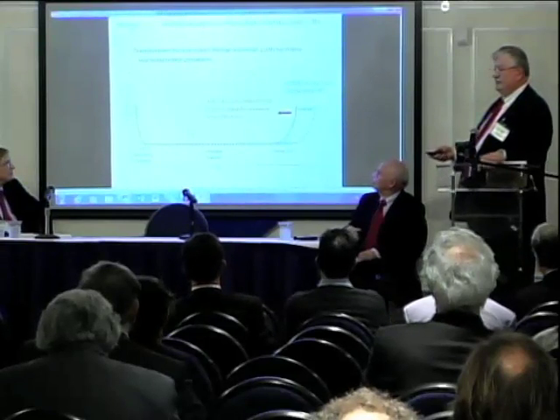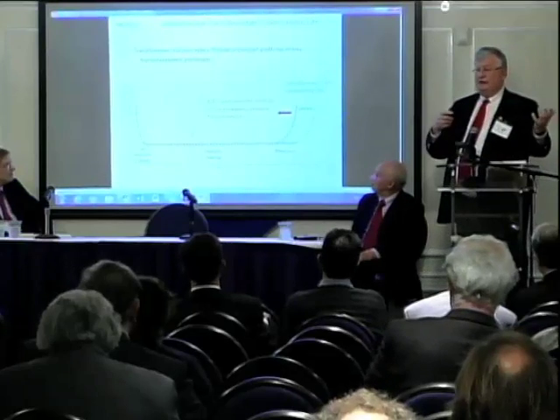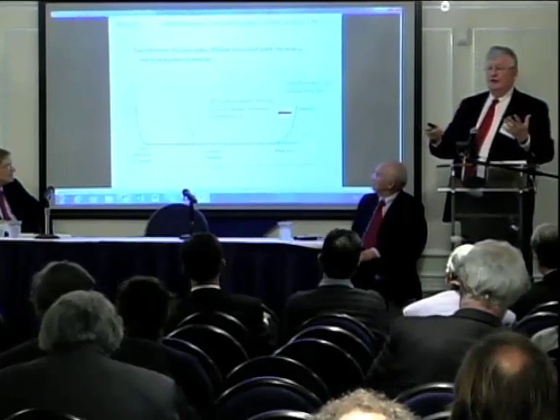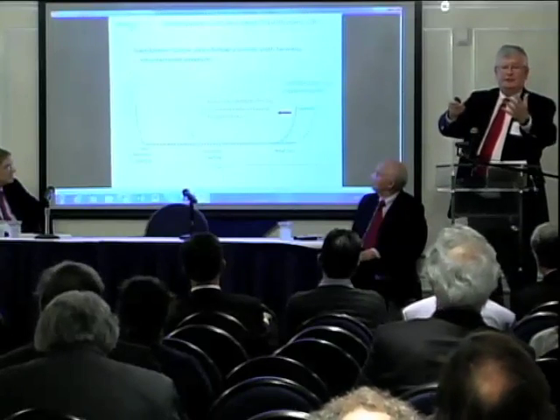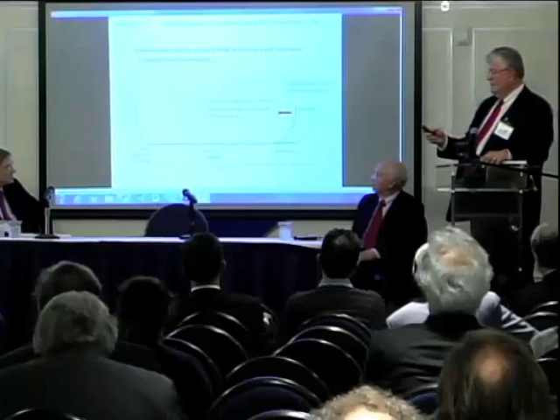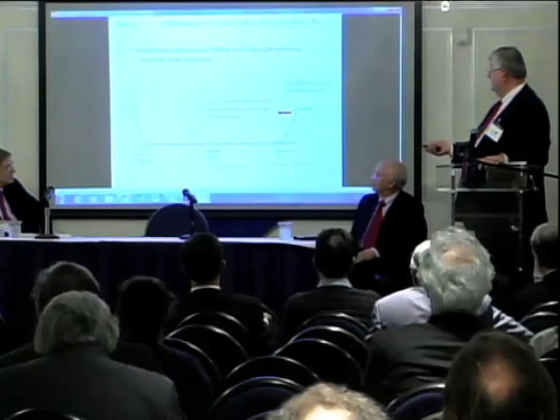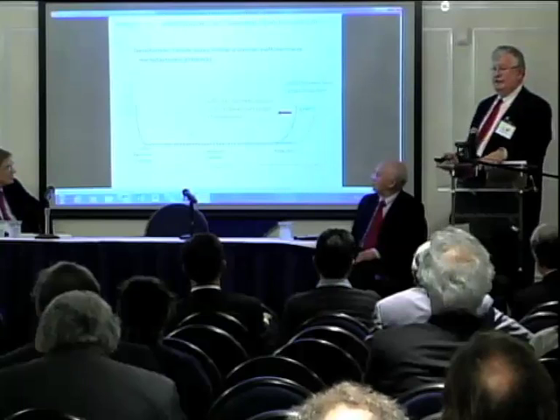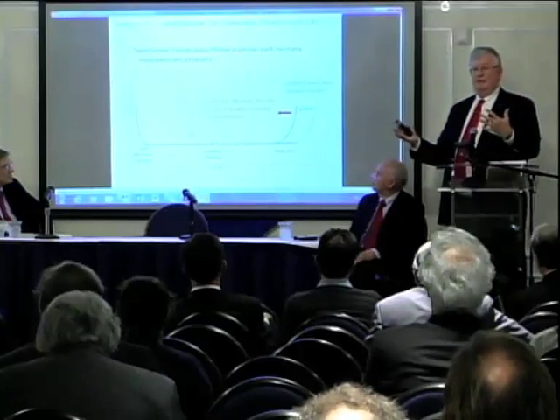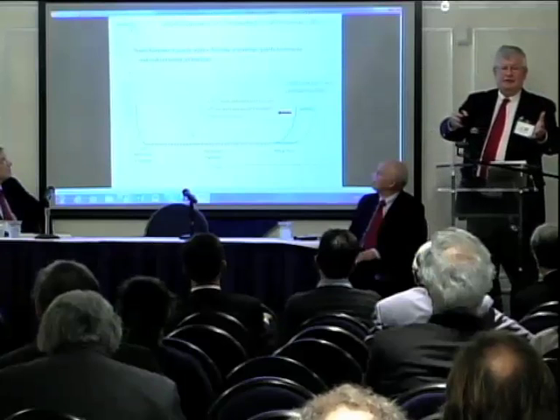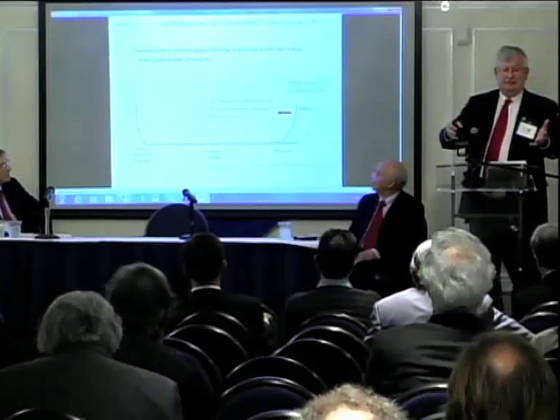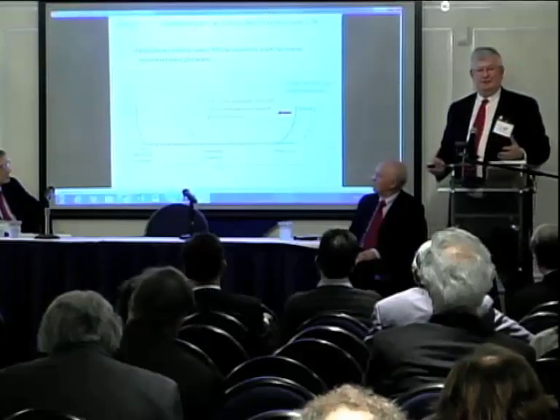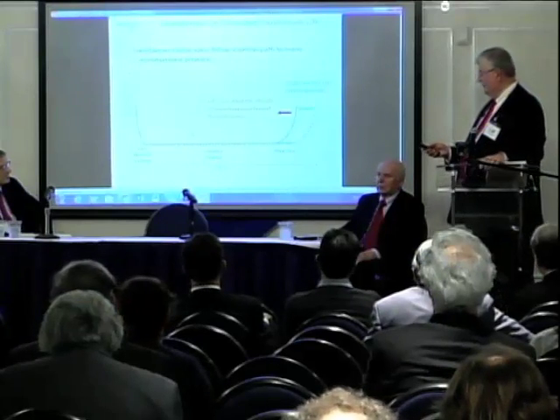We also think that when transformers are humming and shaking, or you get 1,000 amps or 3,000 amps in the neutral, blocking can certainly save the life or extend the life of a transformer. The average age of transformers today is 42 years, so we're talking about an old fleet to begin with.